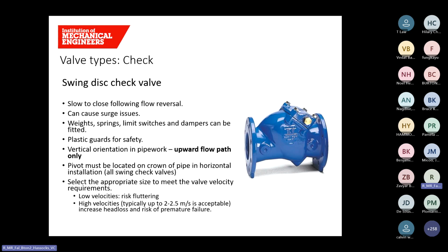Flow velocities. There's a typical range of suitable flow velocities for this valve, and that's between about 1 and 2.5 meters per second, but the suppliers will give you the specific requirements for their valve. But if the velocities are low, there's a risk of the valve not opening fully, and you can have a fluttering effect on the valve. And if the velocities are too high, then your head loss increases, and you can also have premature failure of the valve.